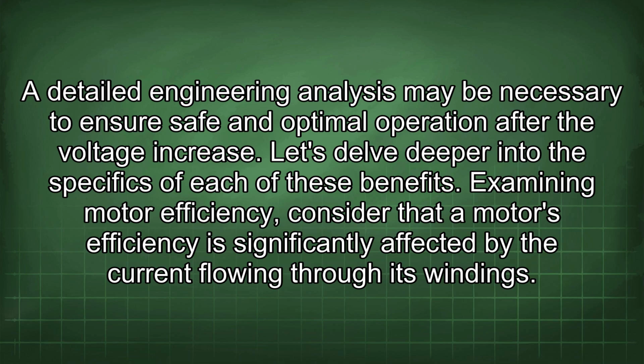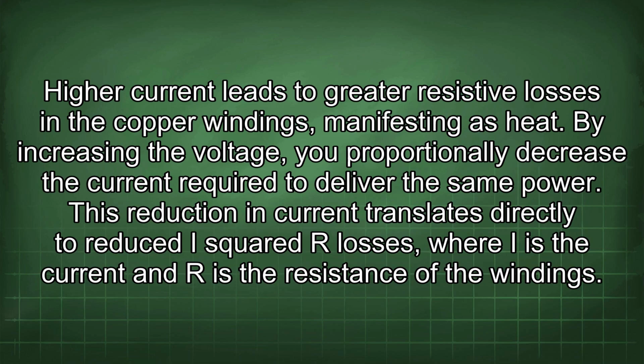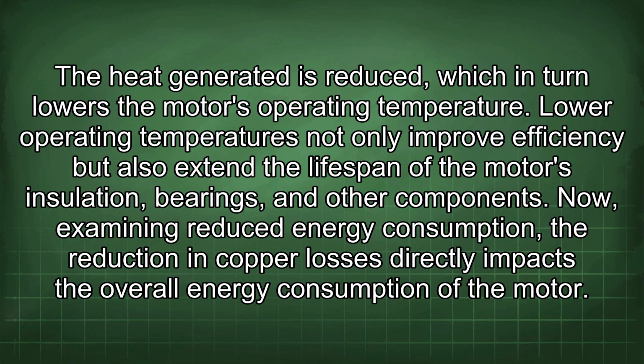Examining motor efficiency. Consider that a motor's efficiency is significantly affected by the current flowing through its windings. High current leads to greater resistive losses in the copper windings, manifesting as heat. By increasing the voltage, you proportionally decrease the current required to deliver the same power. This reduction in current translates directly to reduced I²R losses, where I is the current and R is the resistance of the windings. The heat generated is reduced, which in turn lowers the motor's operating temperature. Lower operating temperatures not only improve efficiency but also extend the lifespan of the motor's insulation, bearings, and other components.